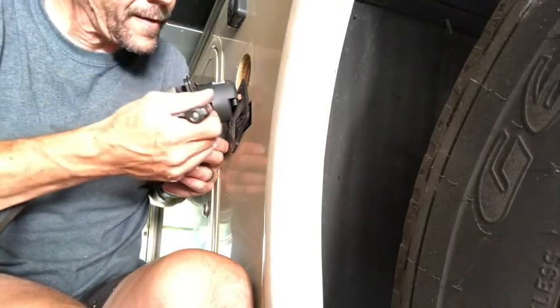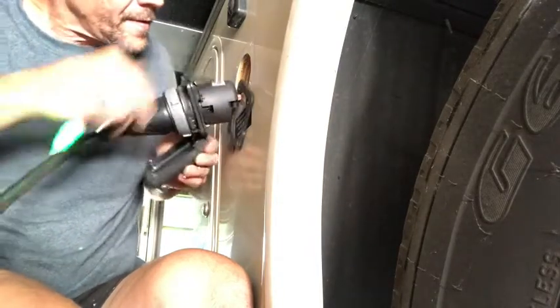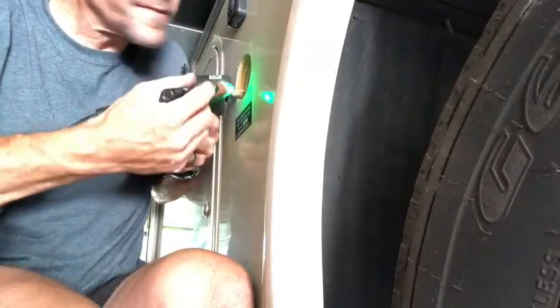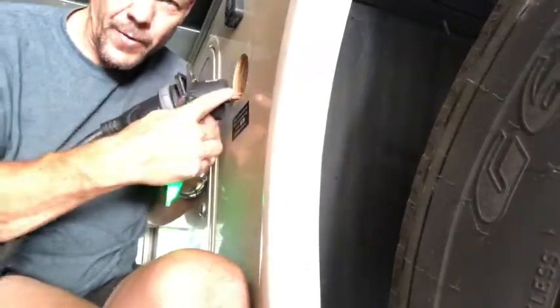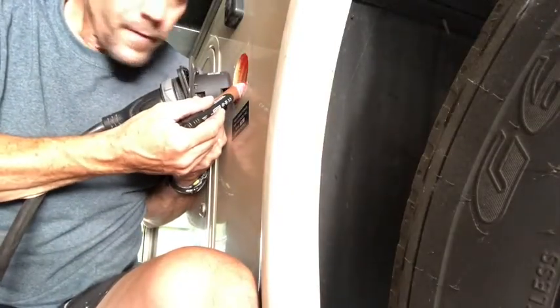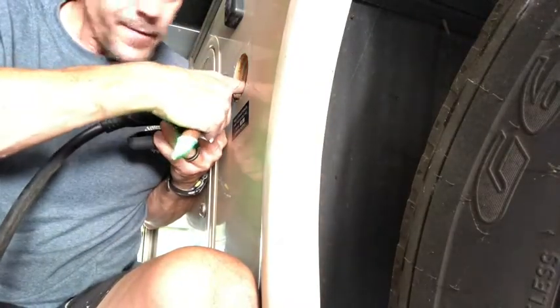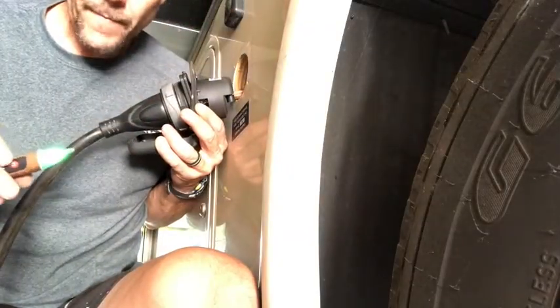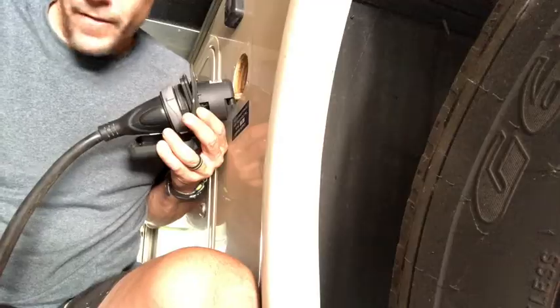Okay, so we know this receptacle's okay because I'm getting power to this wire. Just for giggles, we can check this little bit of Romex that's exposed here. I've got 110 volts going to the Romex that goes into the rig, so this receptacle is okay.